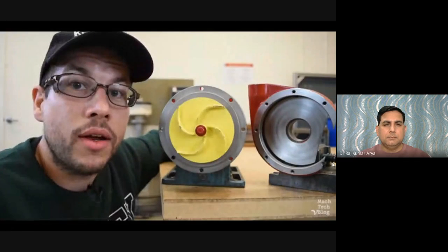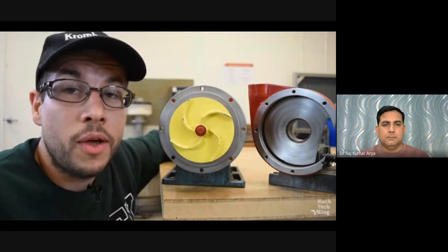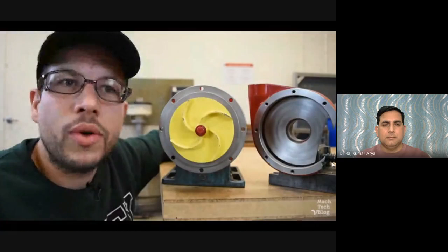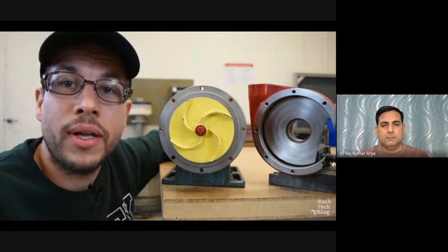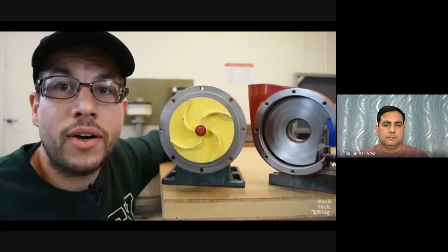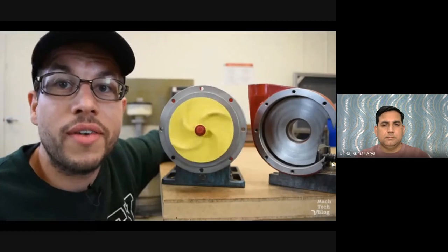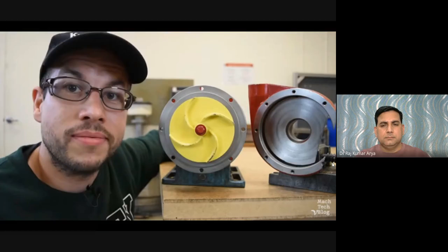Well, that's not really what the vanes are there for. The vanes' purpose is to conduct the fluid along the smoothest possible path as it travels through the pump. Backwards curved vanes help to stabilize flow conditions at high speeds and reduce demands on the motor. The correct rotation for this impeller is actually counterclockwise. And you can always tell the correct direction of rotation of an impeller just by looking at the way that the vanes are curved.